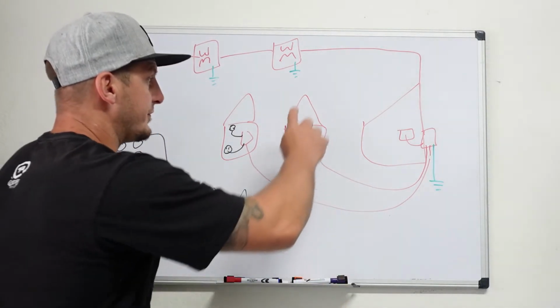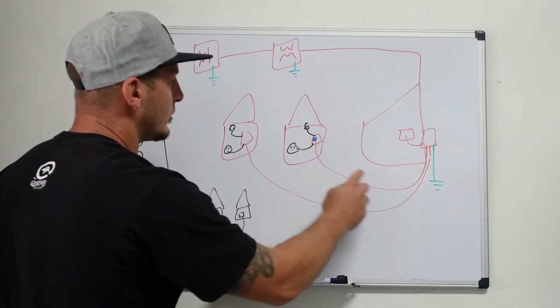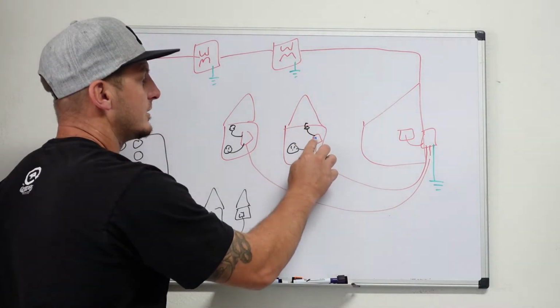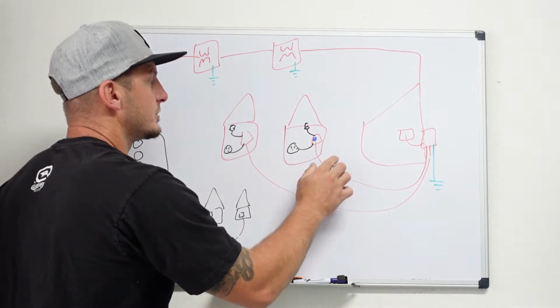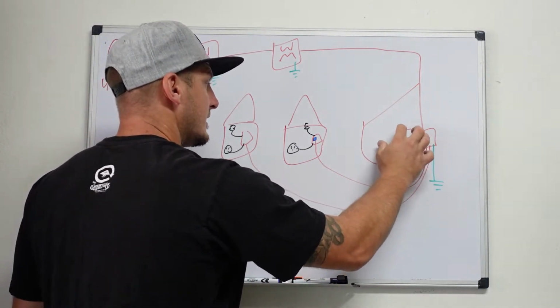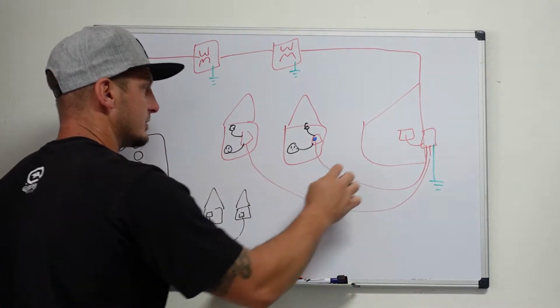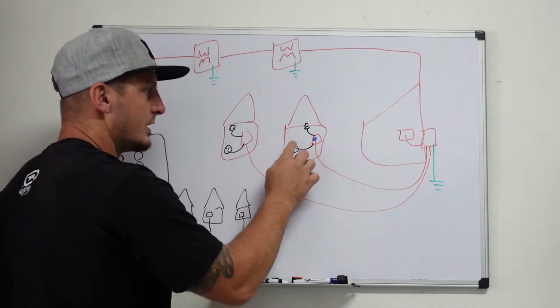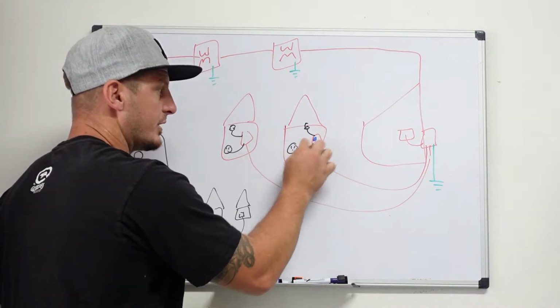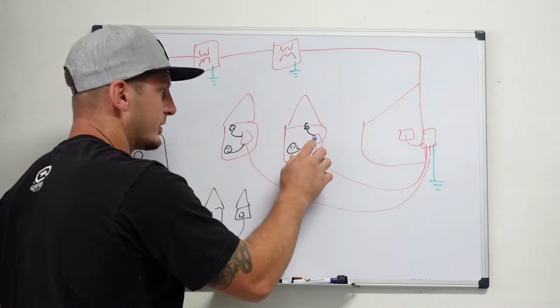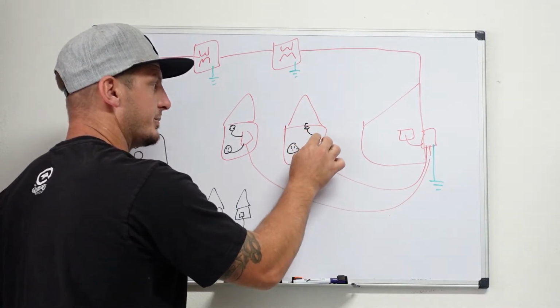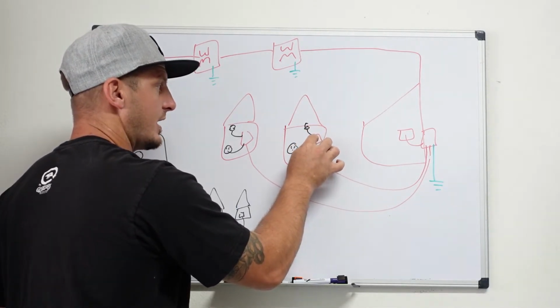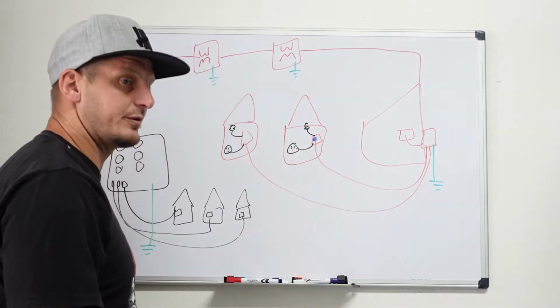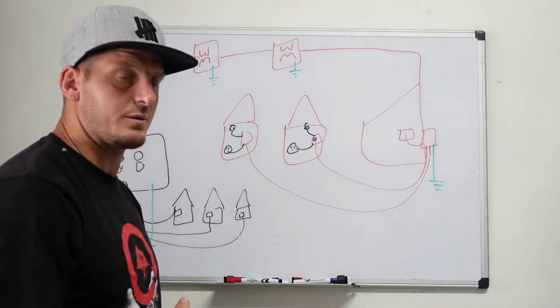In this situation, it's only protecting loads coming out of this panel - not anything in the other condos. So if you have two sub panels feeding a house, it wouldn't protect all the loads in that house, only the loads coming out of this specific sub panel. So if you have more than one, you'd want to protect each one.